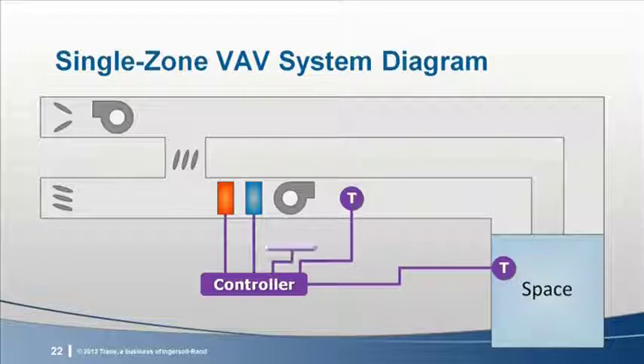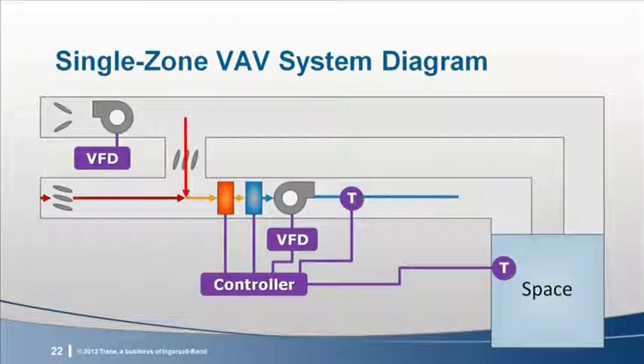The Single Zone VAV system combines the simplicity of a constant volume system with the energy savings of a VAV system. The Single Zone VAV system uses a variable volume supply fan and cooling and heating coils. There's no need for a VAV box in the supply airstream because the system delivers the proper amount of tempered supply air to meet the load in the zone. A zone temperature sensor signal is used by the system controller to control discharge air temperature, supply fan speed, cooling coil operation, and heating coil operation. The cooling coil is controlled to a single discharge temperature. This is a change from the constant volume system. The space temperature sensor, by way of the system controller, determines the system operation. John's going to show us how a Single Zone VAV system is controlled with an example control sequence.